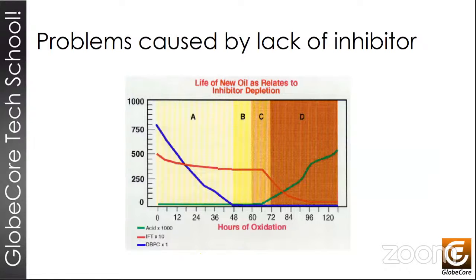In this graph, we can see what happens when we don't have oxidation inhibitors. You will see that at a certain point, the oil begins to undergo significant changes. Please take a look at the green curve and the red curve. We can see the point when interfacial tension, that's the red line, drops sharply, and the neutralization number, or acidity of the oil, that's the green line, begins to increase sharply. And it happens quite soon after the inhibitor is completely exhausted.